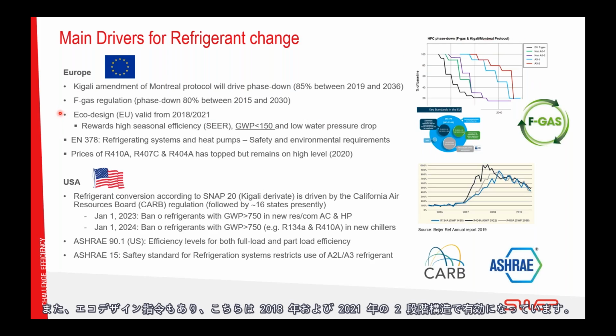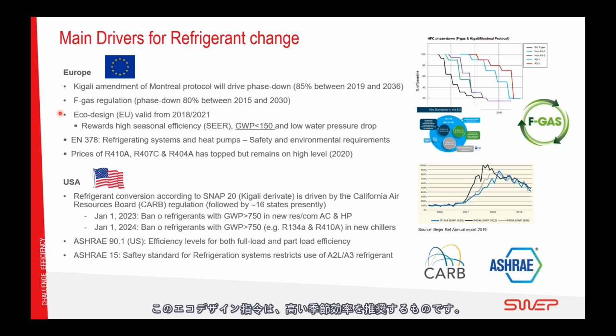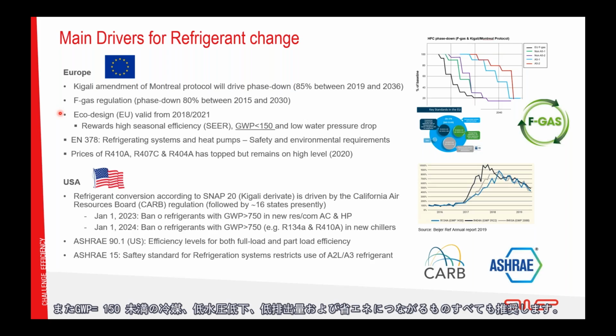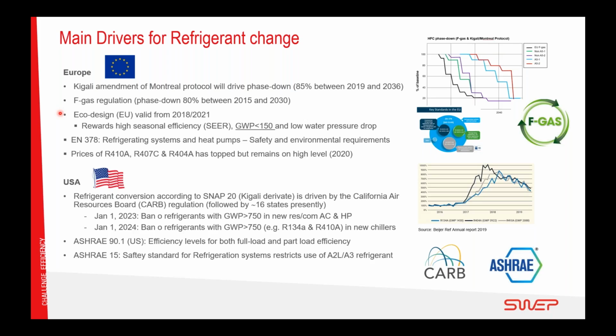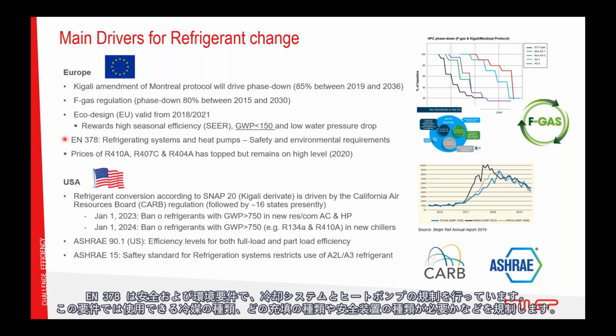We also have the eco-design, which is valid 2018 and 2021 in 2 tiers. And this eco-design rewards high seasonal efficiency. It also rewards if you have a refrigerant below 150 and low water pressure drop. Everything contributes to lower emissions and energy consumption. The EN 378 is the safety and environmental requirements regulating refrigeration systems and heat pumps. It regulates what type of refrigerant you can use and what type of charge and what type of safety equipment needed.